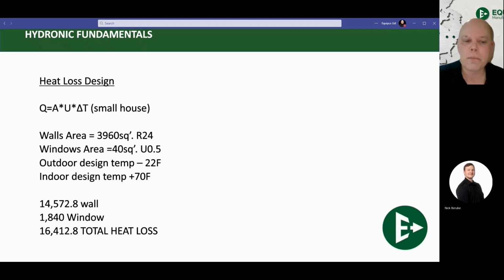One thing to take note of is that when we did this whole home heat loss of 1,200 square feet, we only had a 16,500 BTU heat loss, which is very small. And I want you to think, can you even think of a furnace or a boiler that has a heat output of 16,000, 17,000 BTUs? Very unique situations possibly, but for the most part, you're going to have to design a system that will give you this sort of BTU output without short cycling and destroying the system.